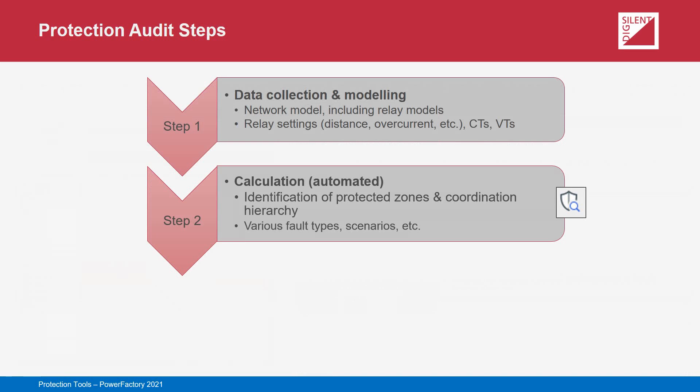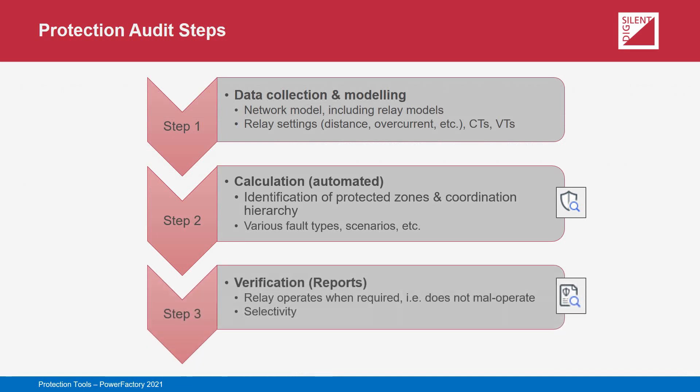Various static short circuit calculations can then be carried out considering any number of different fault types. For each fault, the response of the relays is captured for further analysis. The whole process can be repeated any number of times, each time considering different operating scenarios. The final step is to present and verify the captured data. An additional reporting command is available that can generate three different reports: a report verifying relay operating times, a report verifying fault clearance times where the operating time of circuit breakers is additionally considered, and a report verifying device coordination. All reports are tabular, colour coded, and interactive.